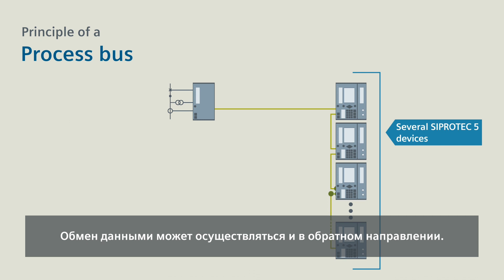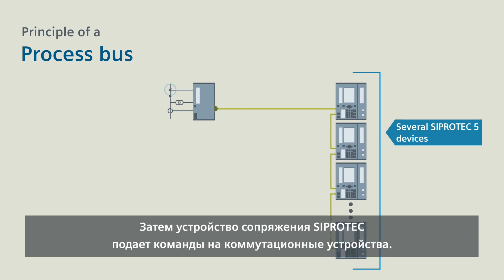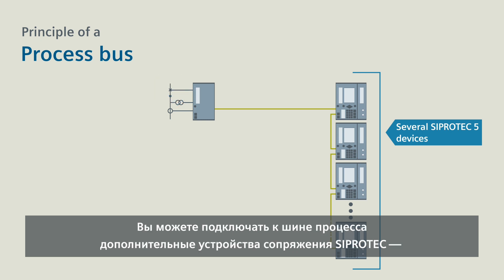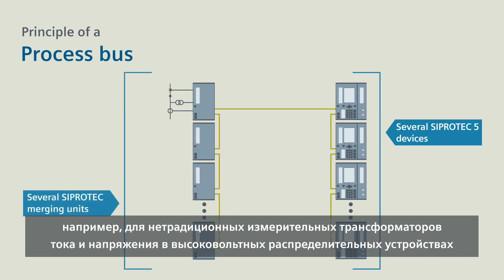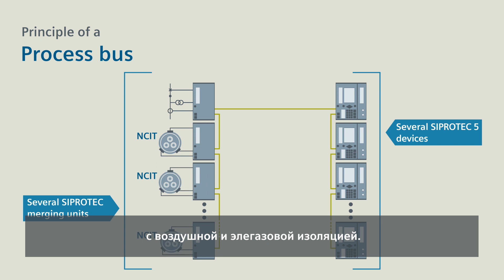Communication also works in the opposite direction. The SIPROTEC merging unit then outputs commands to the switching devices. You can connect further SIPROTEC merging units to the process bus, for example for non-conventional instrument transformers in air-insulated and gas-insulated high-voltage switchgear.